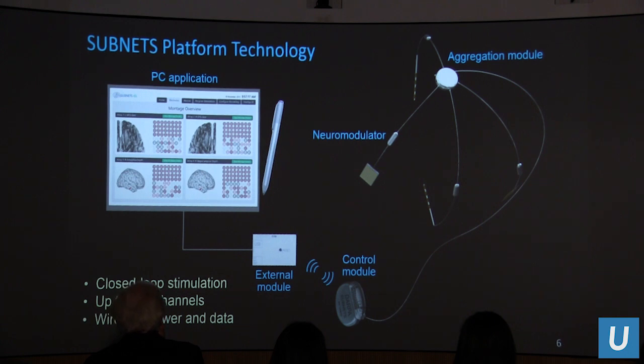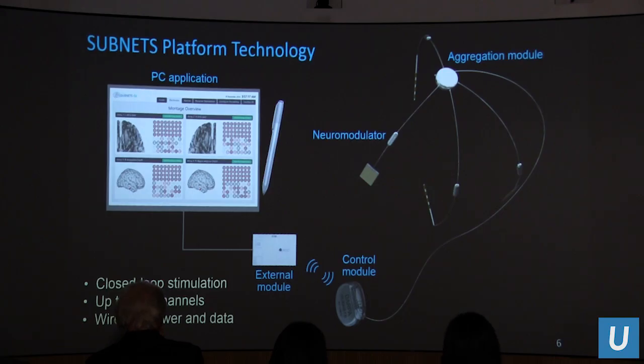This is the platform technology we developed for SUBNETS. In four years, we went from zero to a full system with an external tablet touchscreen PC application allowing clinicians to program parameters into the device, select recording areas, and prescribe open-loop or closed-loop therapy. We have an external device to program the implant using modern wireless power delivery for battery charging and wireless data telemetry, an aggregation module for data management, and neuromodulators implanted on the skull that perform closed-loop interaction with the brain.